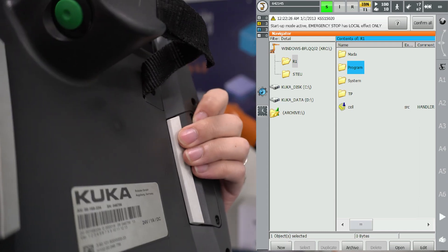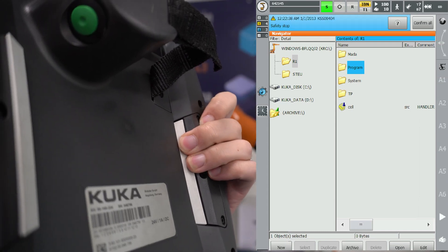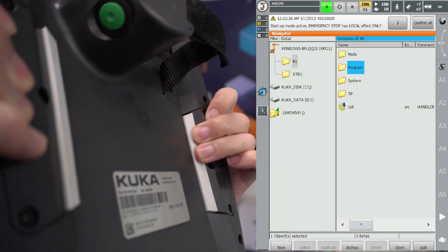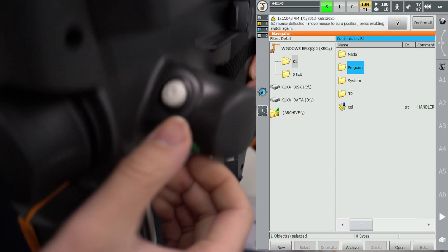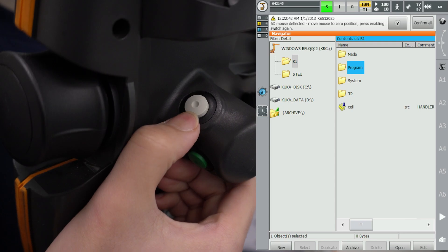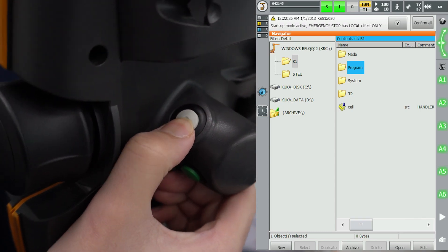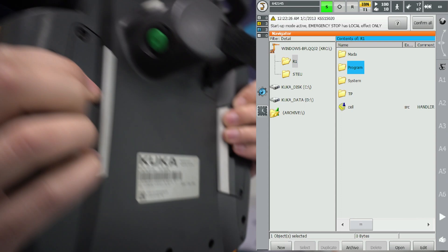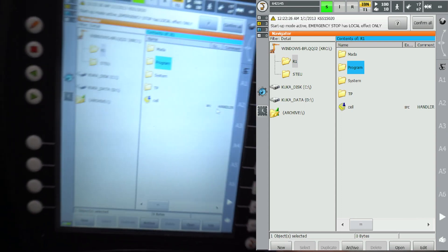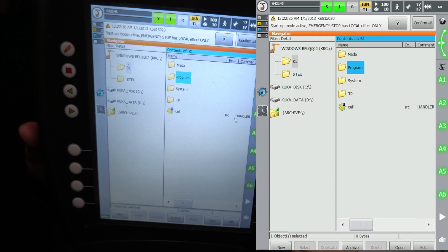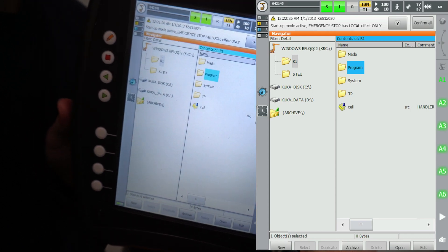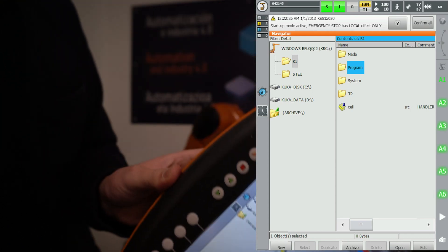These are the handbrakes. They have two positions. If you push hard it goes into the second position. If you push soft it goes into the first position. The first position is the one that enables movement and everything turns green on the screen. This is designed to stop the robot's movement immediately in case of accident. Some people tend to tense their muscles and grip harder and others lose control of their muscles and let go.